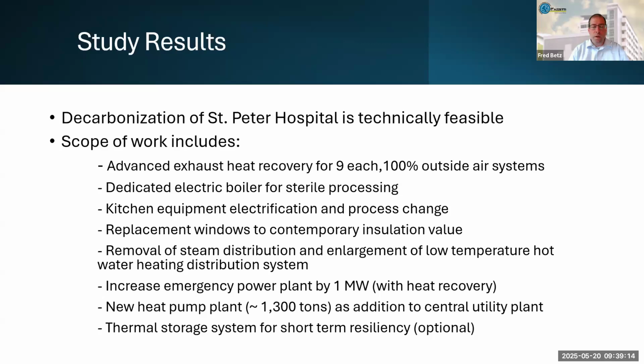One little nuance there is we're using the generators as a cogen system, but only for emergency use. So if those generators are operating in the winter and there's heat demand, for every megawatt of power a fuel oil generator makes, about 1 megawatt of jacket heat and 1 megawatt of exhaust heat, give or take, is generated. And so we're able to use that jacket heat during a power outage and essentially have a heat recovery system built into our emergency operations. So we get additional heating beyond what we have with the storage and any heat pumps. And I think I touched on heat pumps and thermal storage plenty. So next slide, please.